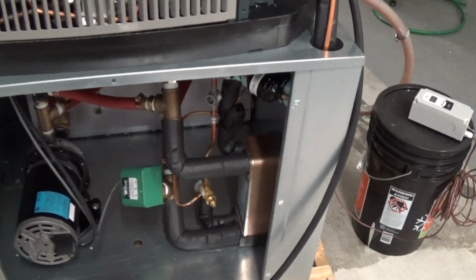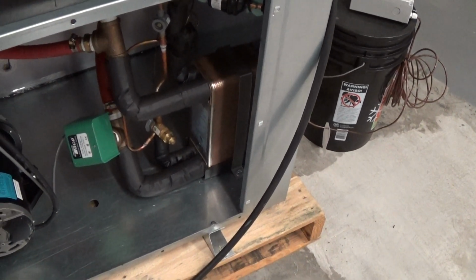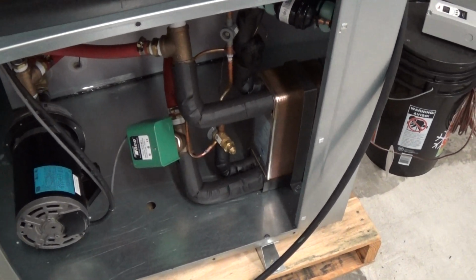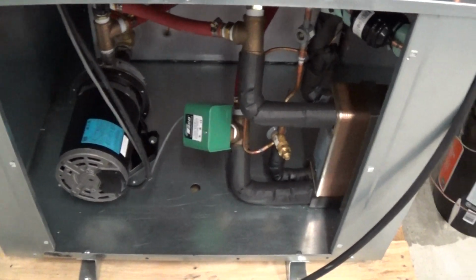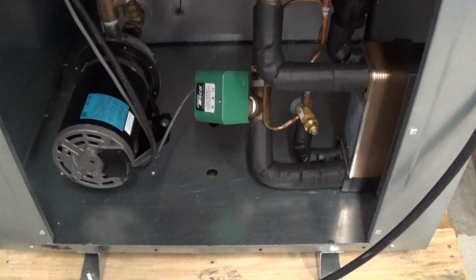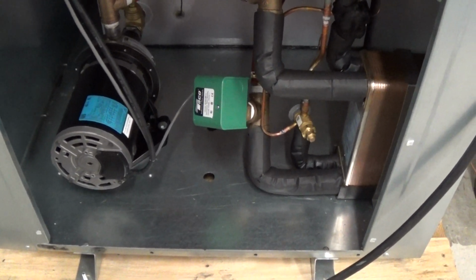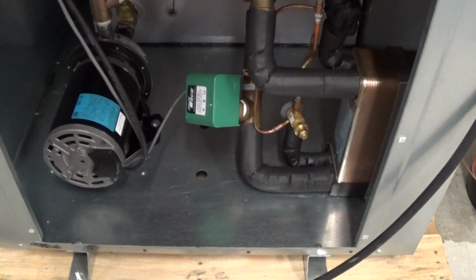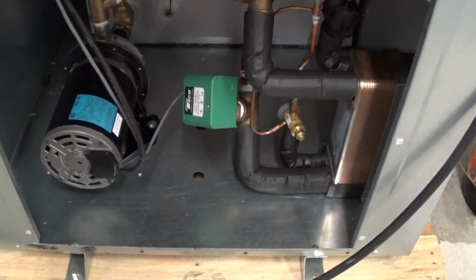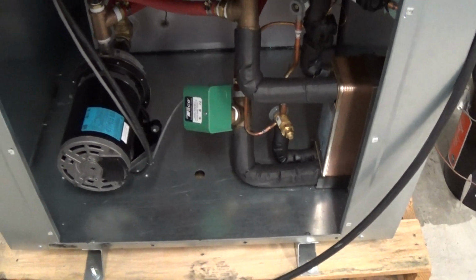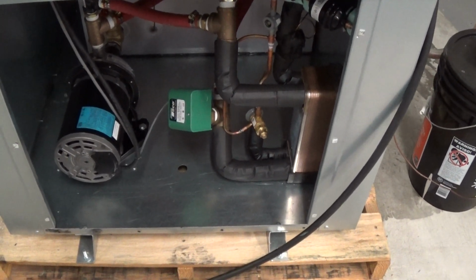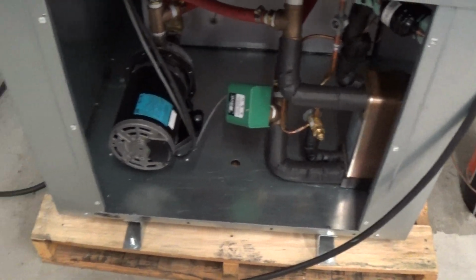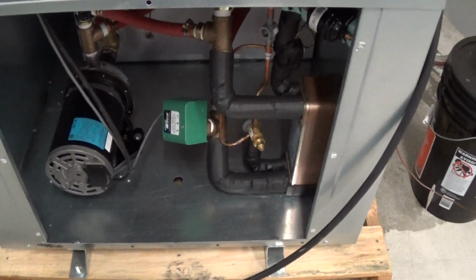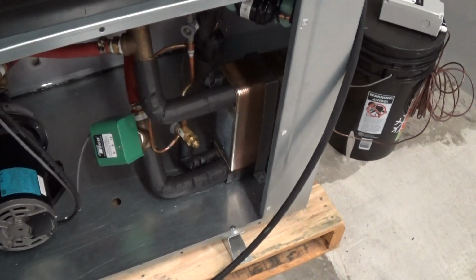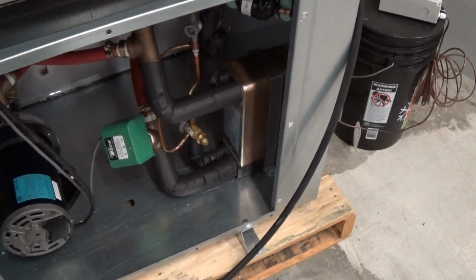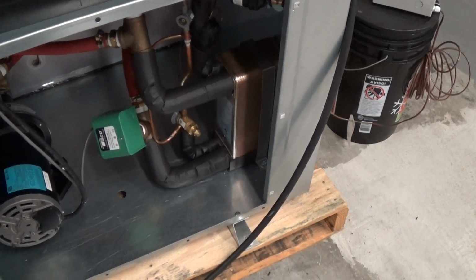I'm going to take a look at some of the components down below. We have our brazed plate heat exchanger, the thermal expansion valve. These units have a flow switch. Flow switch is very important and calibrated at the factory. If we lose flow, we are going to shut off the refrigeration circuit and also the power to the controller. But we will let the pump continue to run, but we're not going to let the refrigeration run because with improper flow we can damage the heat exchanger if the compressor is running.